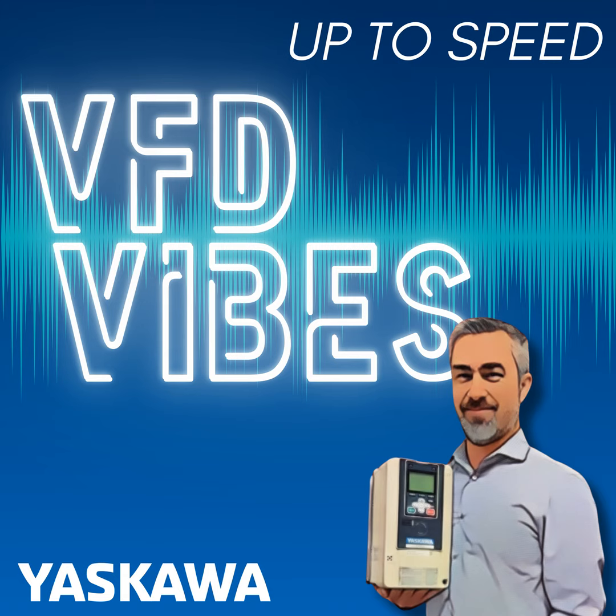So the whole idea of predictive maintenance is to monitor all this data in the system to actually know when these parts are getting close to failure, by monitoring things like vibration - is it normal, is it increasing, is it changing? The current - is it normal, is it increasing, is it changing? It's a cool thing to say, hey, we're at that 12-month point but everything's running A-okay, we're just going to keep monitoring. Then at month 13, alright, now we're starting to see some symptoms - it's time to actually make that change.